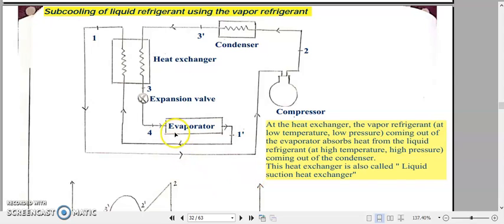Now let us start with the most important portion of this arrangement, that is the evaporator, or our refrigerator, or the freezer compartment. What is happening at the evaporator? Here we have an expansion valve just before this evaporator. The refrigerant coming out of the expansion valve will be a low temperature and low pressure liquid refrigerant. The nature of the refrigerant coming out of this expansion valve will be liquid, but at the same time its temperature and pressure will both be very low. It is this very low pressure, low temperature liquid refrigerant which is going to enter our evaporator.